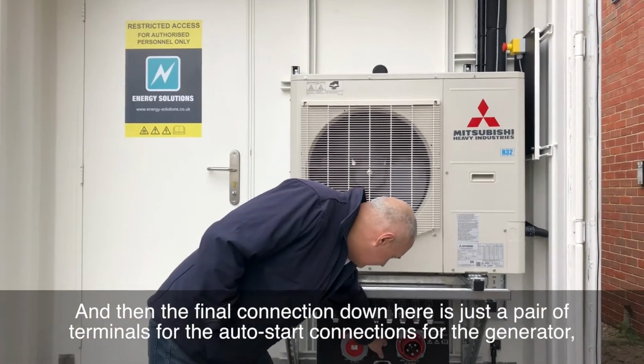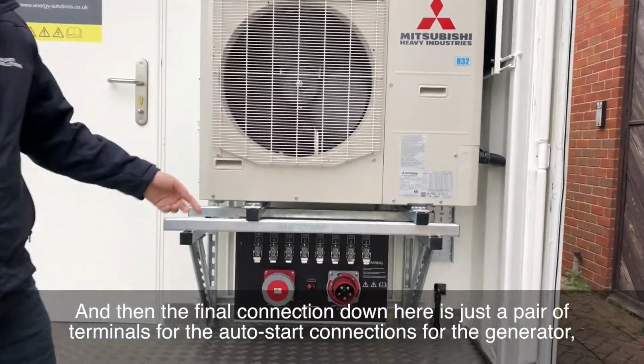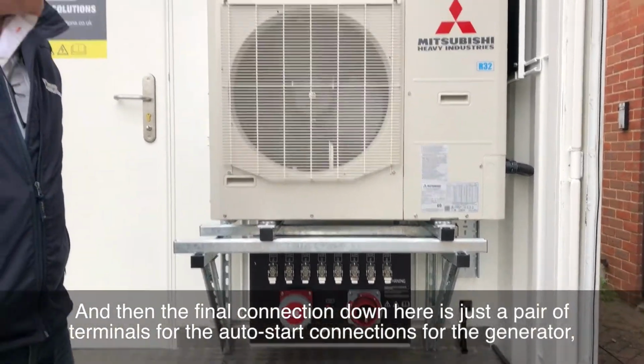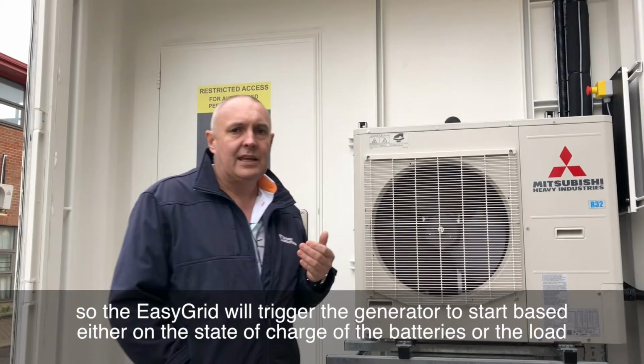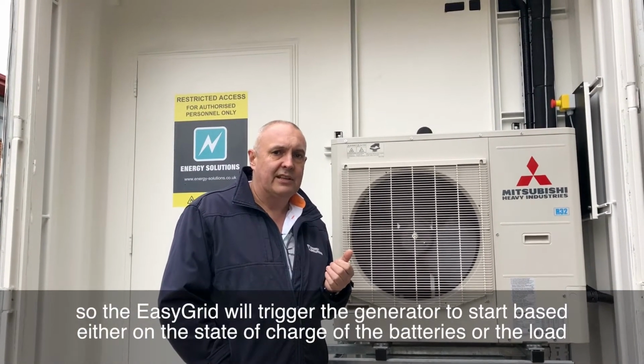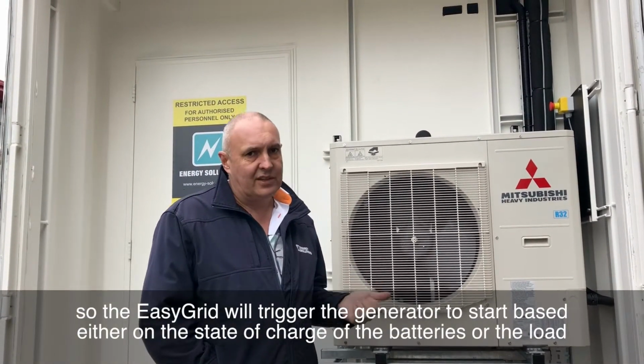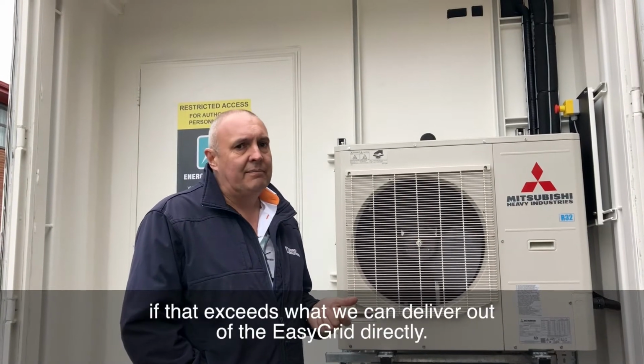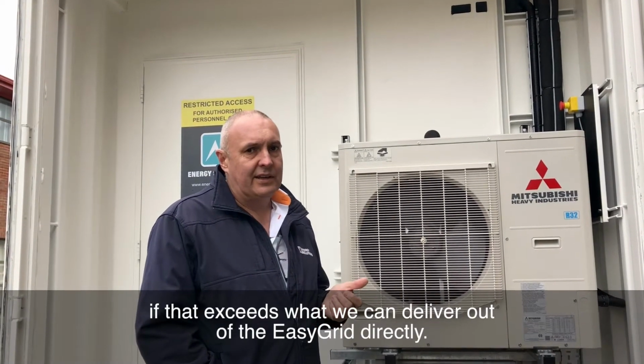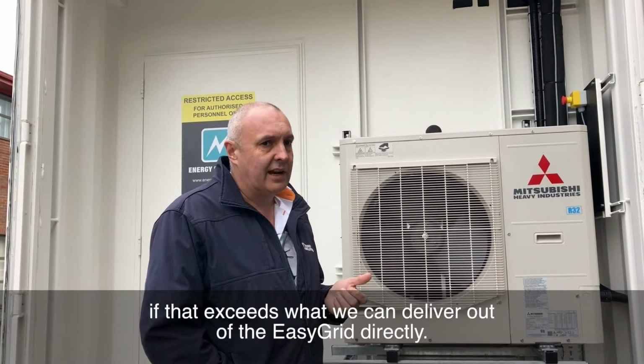The final connection here is just a pair of terminals for the auto start connection to the generator. The EasyGrid will trigger the generator to start based either on state of charge of the batteries or load, if that exceeds what we can deliver directly out of the EasyGrid.